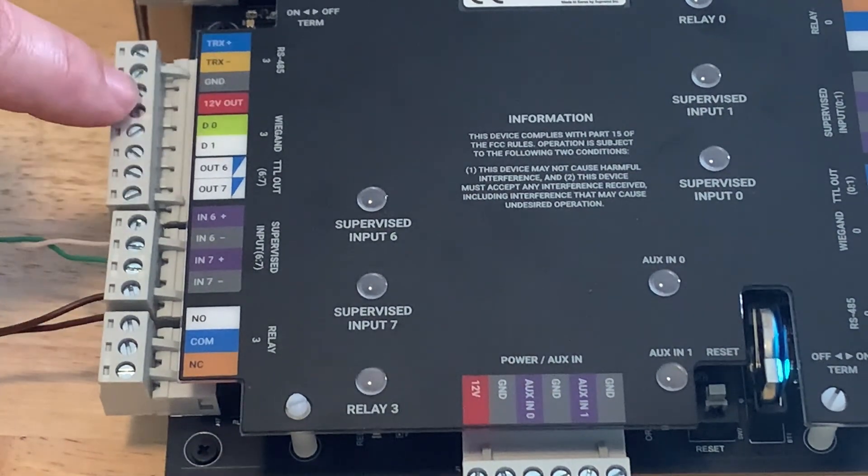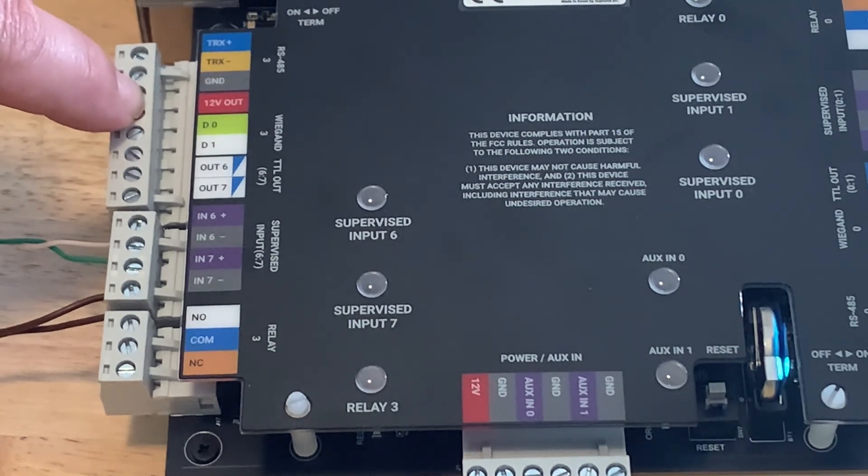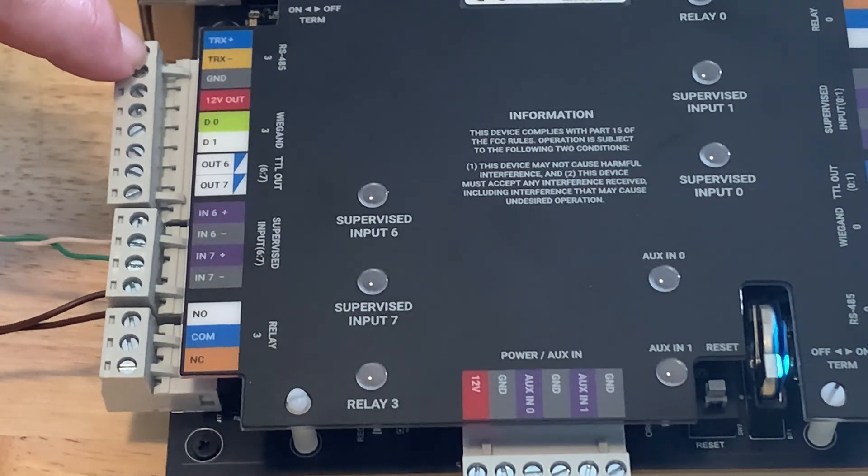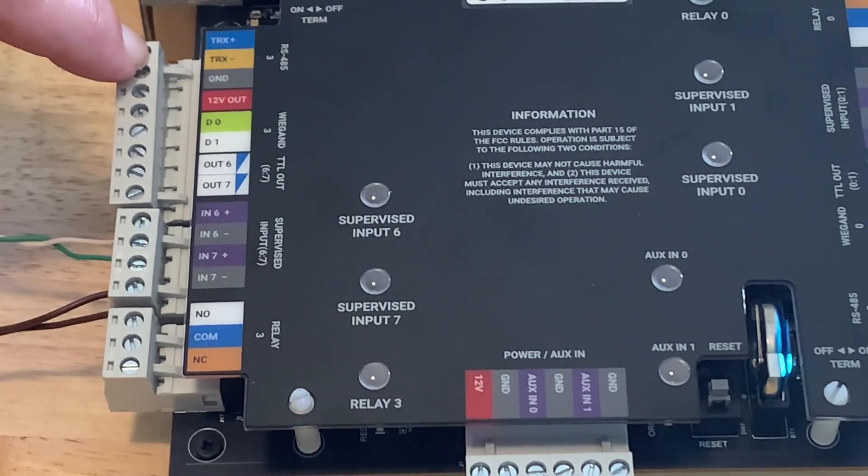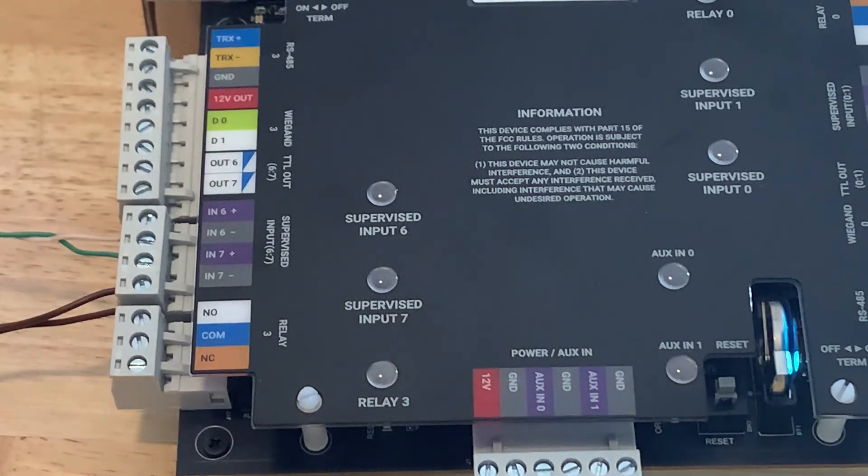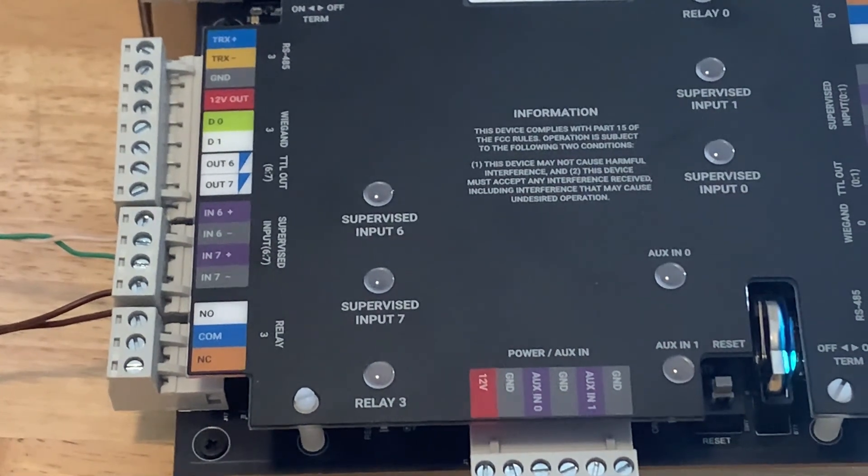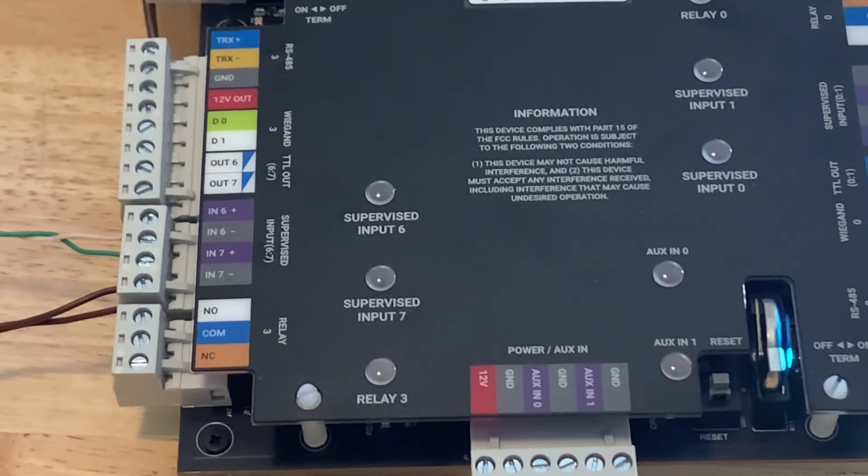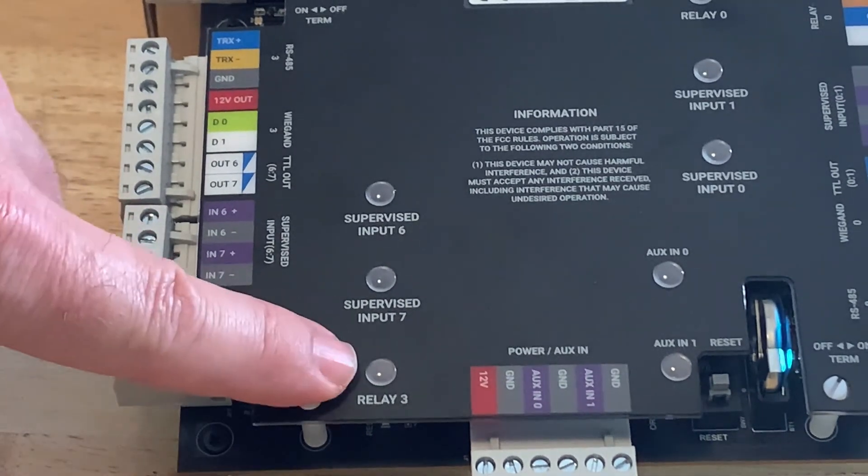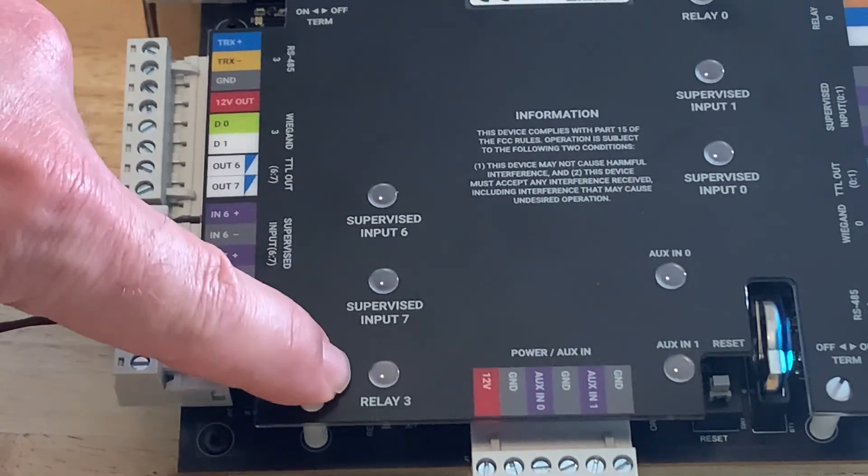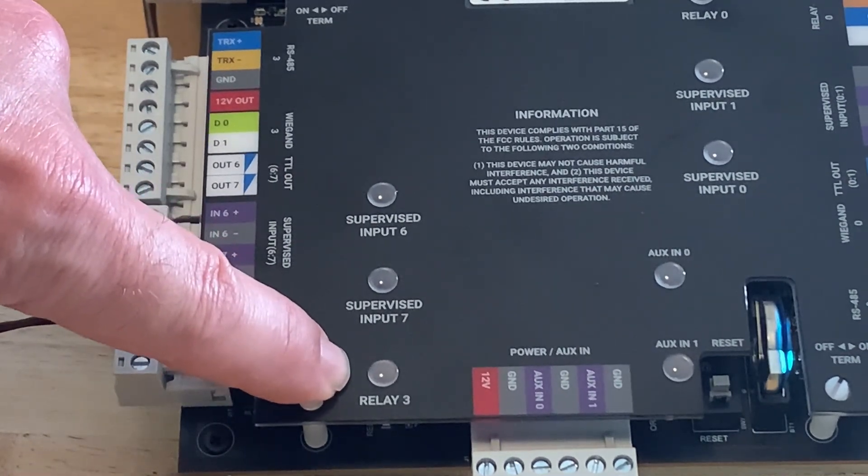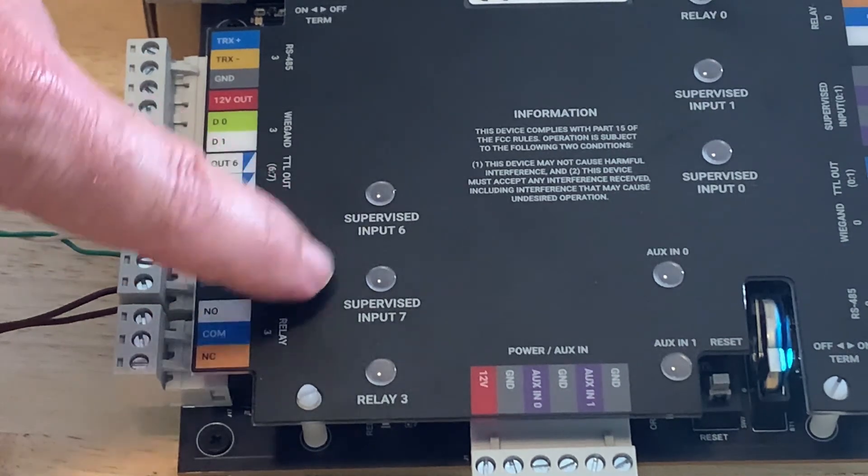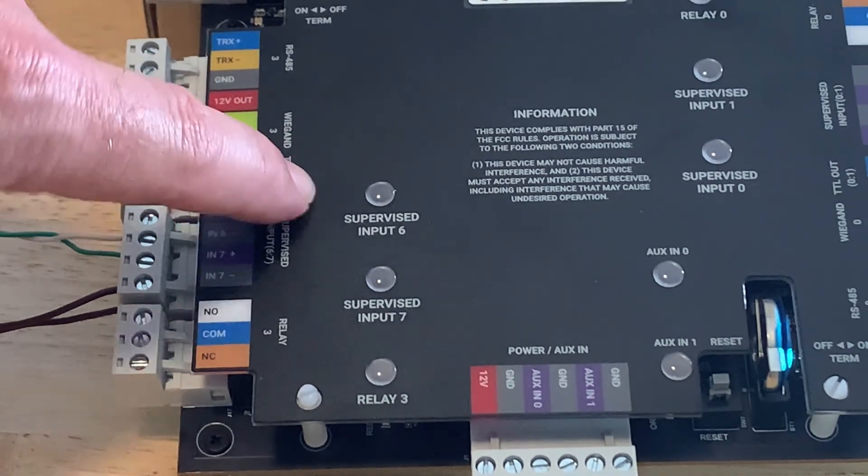And then we have 12 volt DC power out to the readers and then 485 connection at the top here. Now when using our Suprema readers you'll want to use a 485 connection and not the Wiegand connection. As you can see also on each door port we have large light for when the relays trigger as well as lights for the supervisions when they're being triggered and violated.